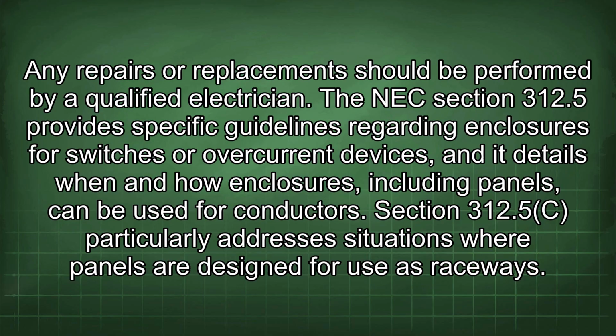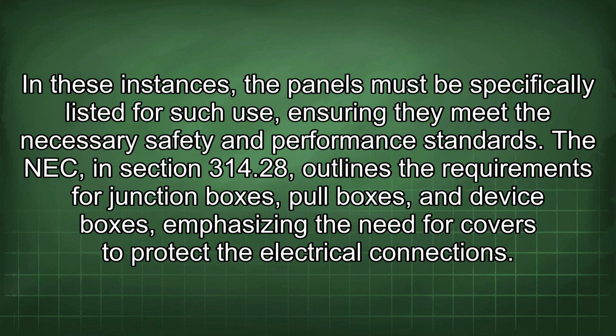NEC Section 312.5 provides specific guidelines regarding enclosures for switches or overcurrent devices, and it details when and how enclosures, including panels, can be used for conductors. Section 312.5(c) particularly addresses situations where panels are designed for use as raceways. In these instances, the panels must be specifically listed for such use, ensuring they meet the necessary safety and performance standards.